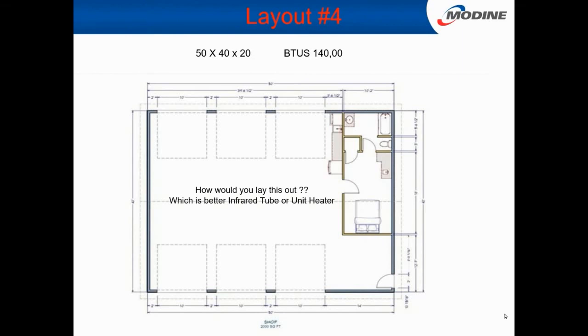How about the placement of the thermostat? Placement of the thermostat usually is located underneath your return air, so wherever it's coming back. On the infrareds, they're probably located on a wall that doesn't see direct vision. Infrareds, if you got your units mounted here, you don't want to put the thermostat there, because it sees that reflection, so it's going to falter. You want to be around the corner, on an opposite wall, someplace where that wall doesn't shine. It shouldn't be in the line of sight of the infrared.